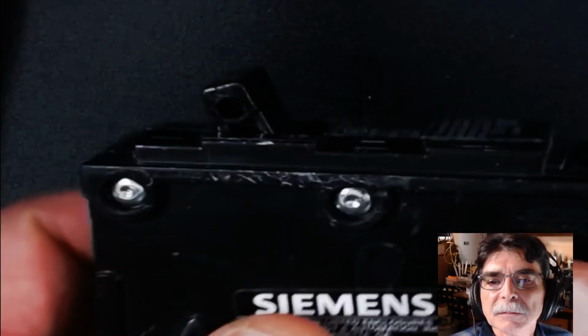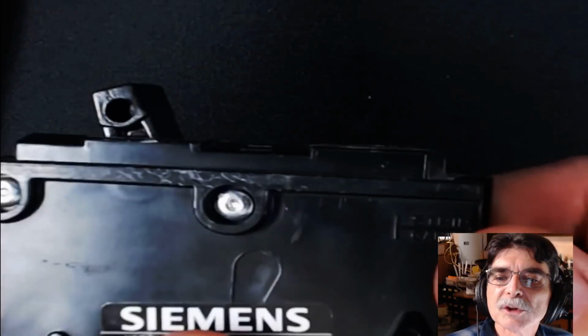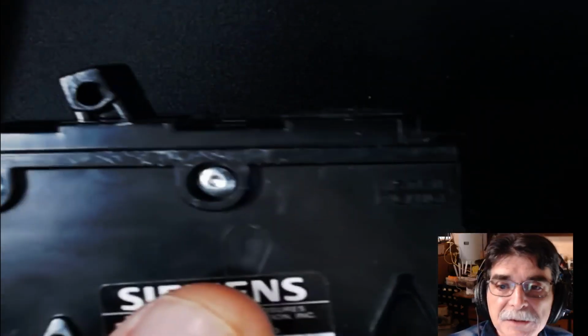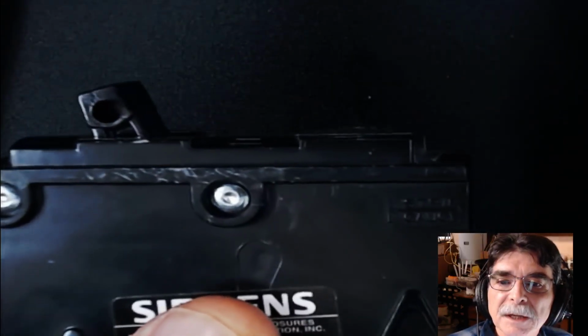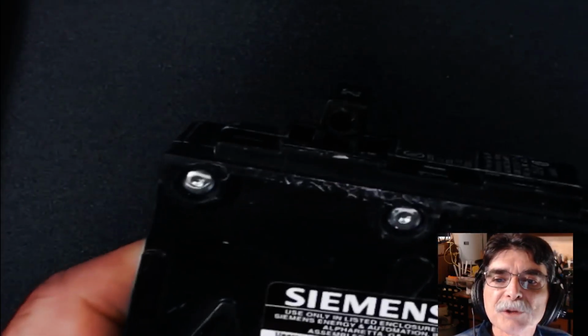You can test circuit breakers. As an electrician, before we ever put them into a panel, we always check them. You just have it open and then whack it on the back of your hand. So what I just did is I tripped the breaker. Do you see the position it's in? It's now 90 degrees.